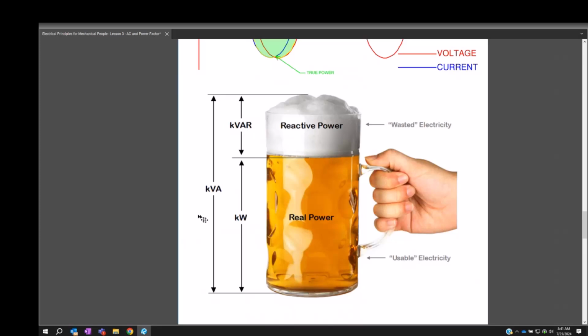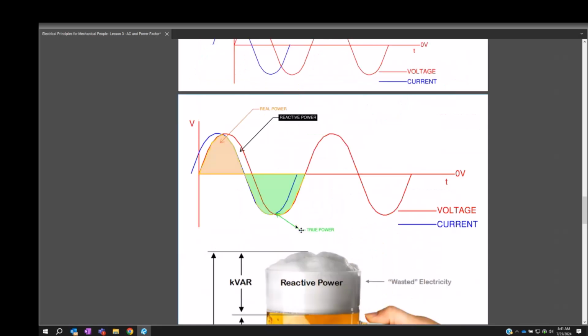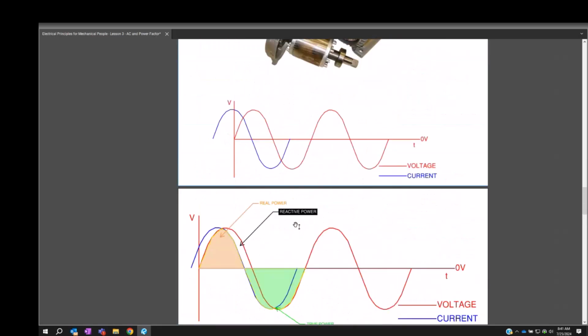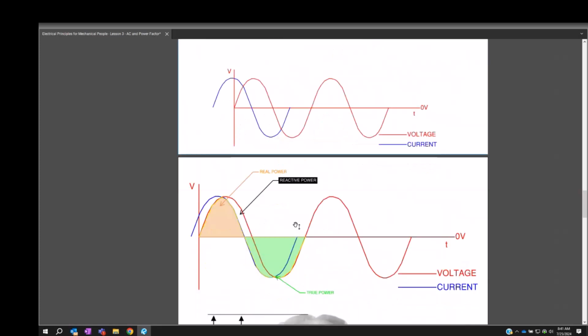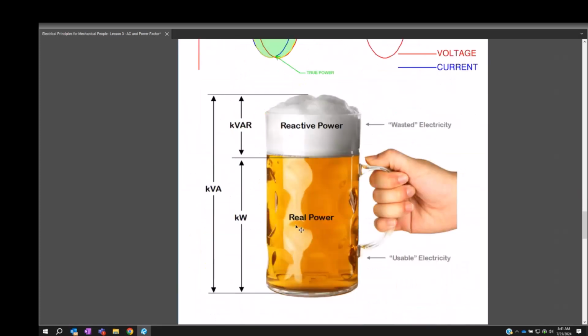So that's when I'm going to be looking at kVA specifically. Is that why when it comes to transformers, I've typically seen them say kVA transformer? Is there any relationship of why? Am I thinking of the right thing? Yes. So yes, when the transformers, like on a pole, on pad mounts, whatever, the transformers are described in kVA because they are describing the total of the kVAR they can support and the kilowatts they can support.